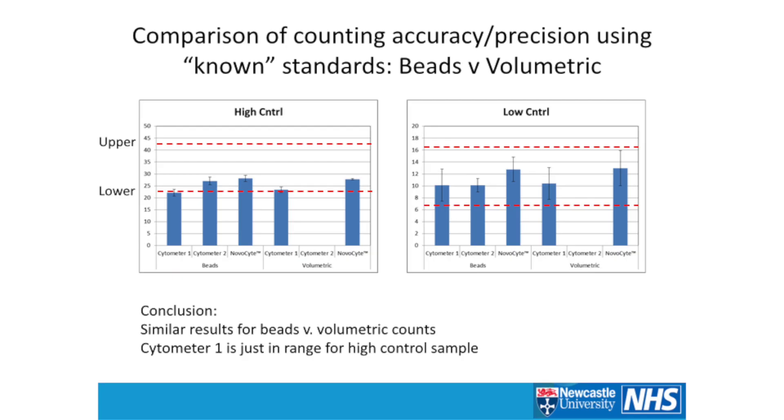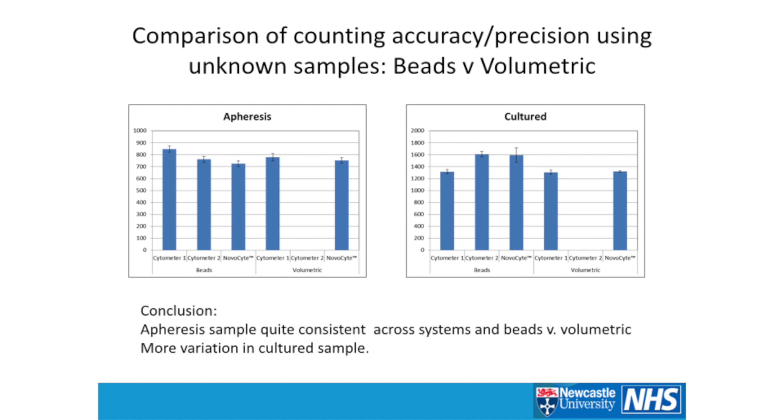We also wanted to look at more challenging samples. A sample from an apheresis stage can be a bit messier, and so can the cultured ones. We can see pretty comparable results — the apheresis sample is quite consistent across systems for beads versus volumetric. The cultured sample shows a little more variation, because it's more challenging to identify positives over background. But the NovoCyte handled it really well.